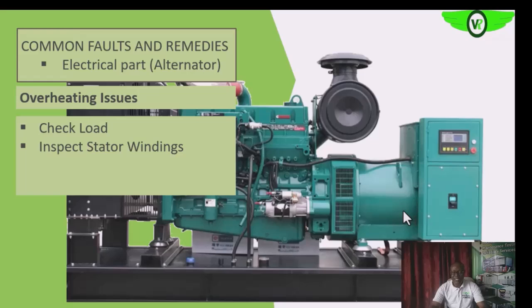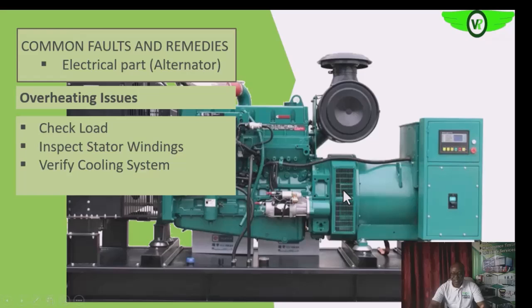Check the load first. Shorted windings within the stator can also result in overheating. The cooling system is also a factor — here we have a fan responsible for cooling the alternator. If it is not effective, or if there is blockage to the cooling area, it will not deliver the required air into the alternator. The heat normally generated will not be evacuated efficiently, and that will cause excessive heating of the alternator.